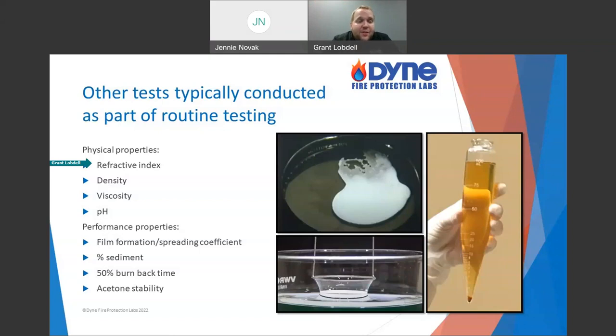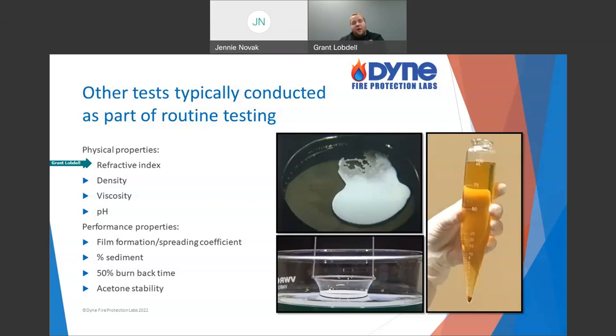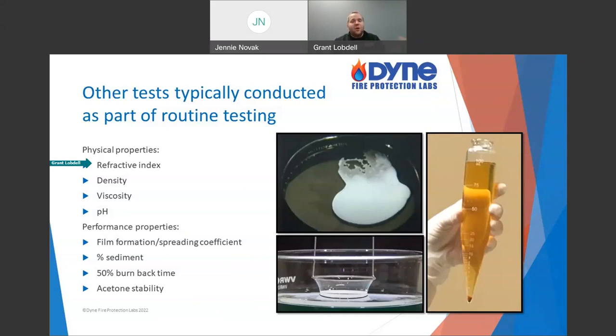These physical properties are compared to how the foam was originally designed. If something looks off, that doesn't mean it fails — we still look at performance properties like expansion, drain time, and film formation to see if it's acceptable. If it does still perform but something was off physically, maybe something occurred but wasn't enough to make it fail. But if there is a performance failure, we go back to those physical properties to ask why. For example, if it has poor expansion, we look at refractive and density — if they're very low, like water, maybe it was diluted.